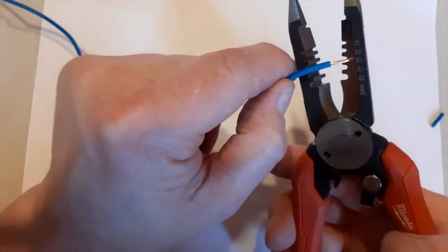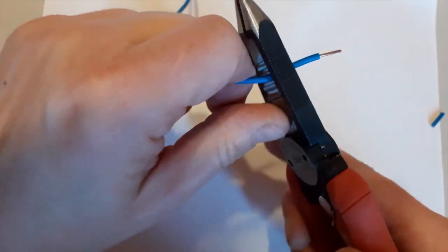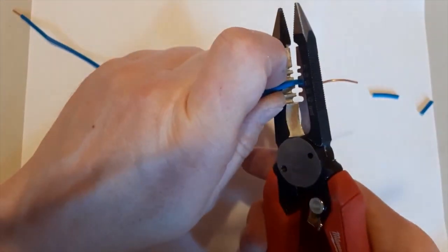There you go, that all feels quite nice. There's no nicks in that. So make sure you get the conductor in the right notch. Using these can be troublesome, takes a bit of getting used to. The cable has to go sometimes quite deep into the pliers to get the right notch, and that can be a bit tight if you're in a back box or something like that.